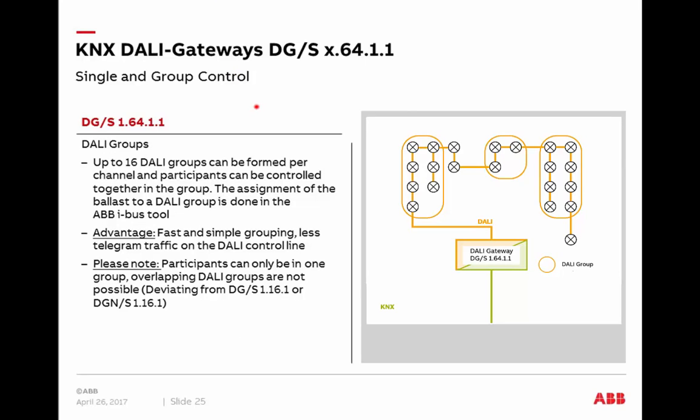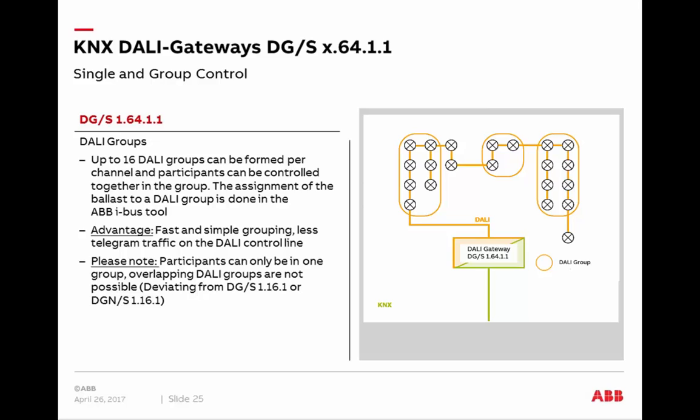We also have DALI grouping available inside these devices. DALI supports up to 16 DALI groups per channel. One advantage is less traffic on the DALI side, because the DALI system recognizes it as a group and only one command is sent. Please note one restriction: a DALI ballast in a DALI group cannot be a member in another DALI group — overlapping DALI groups are not possible. If you need overlapping groups, you must create KNX groups instead.